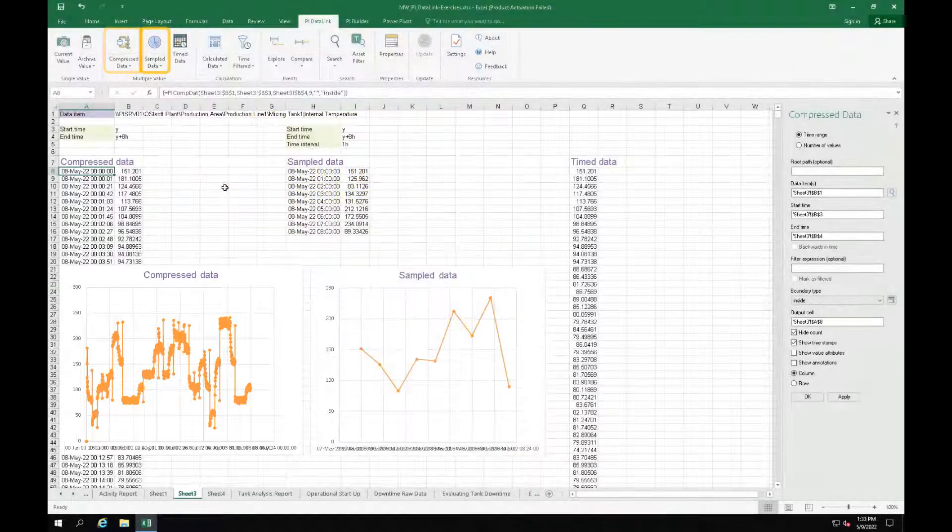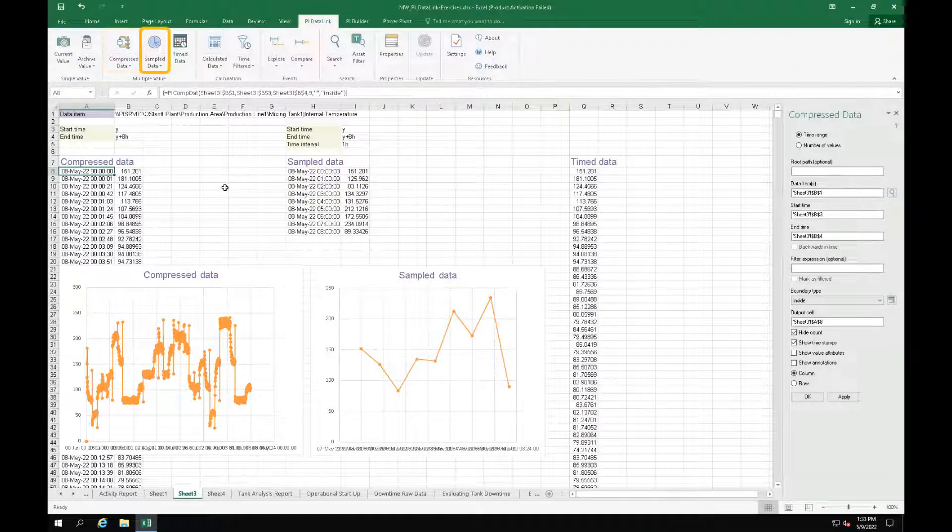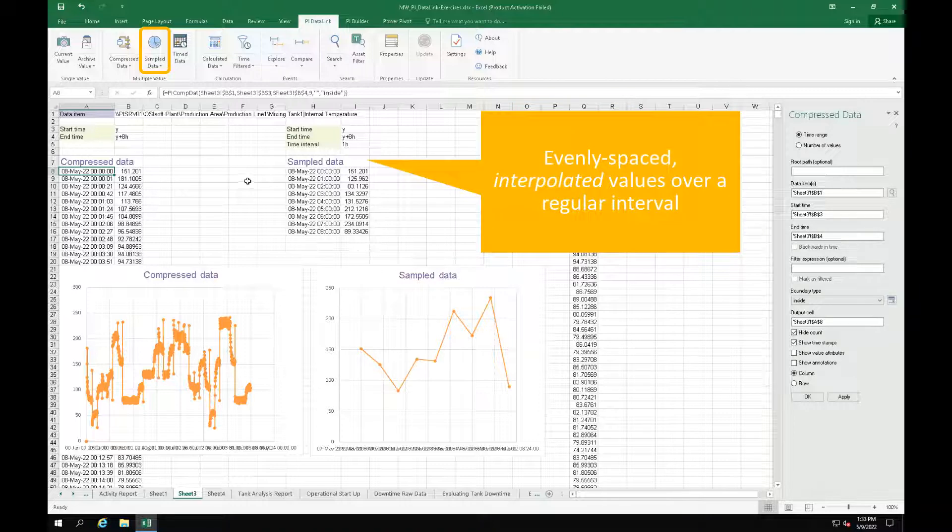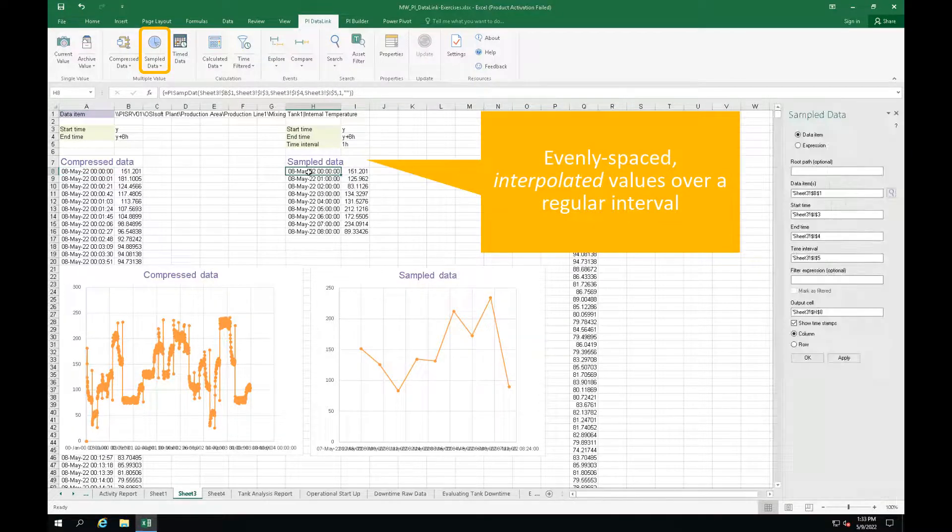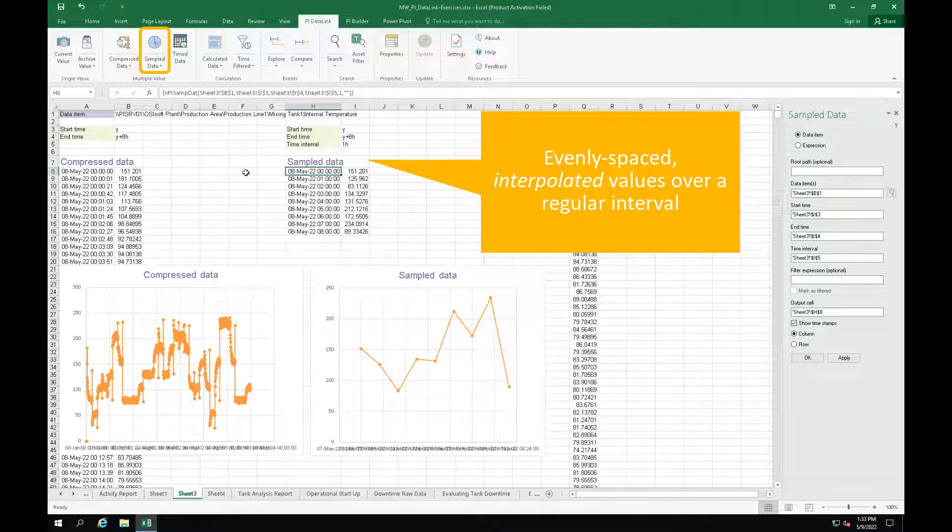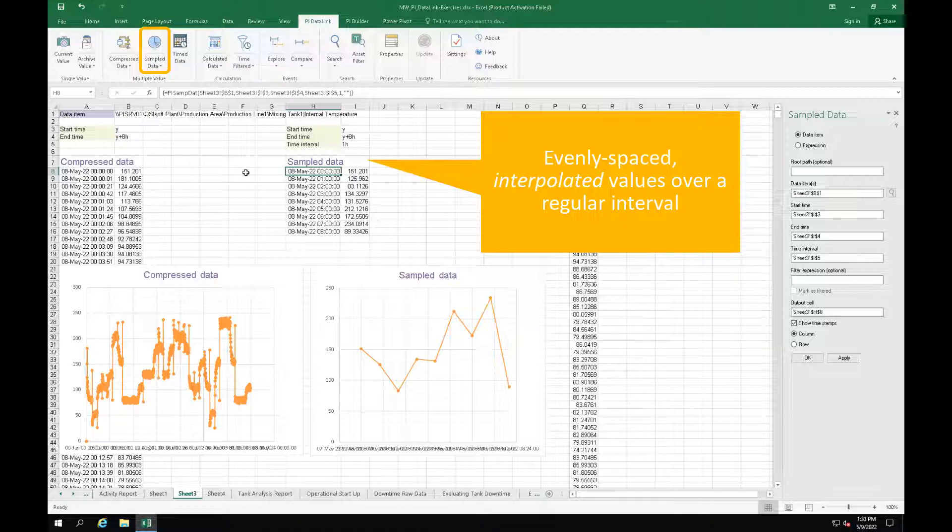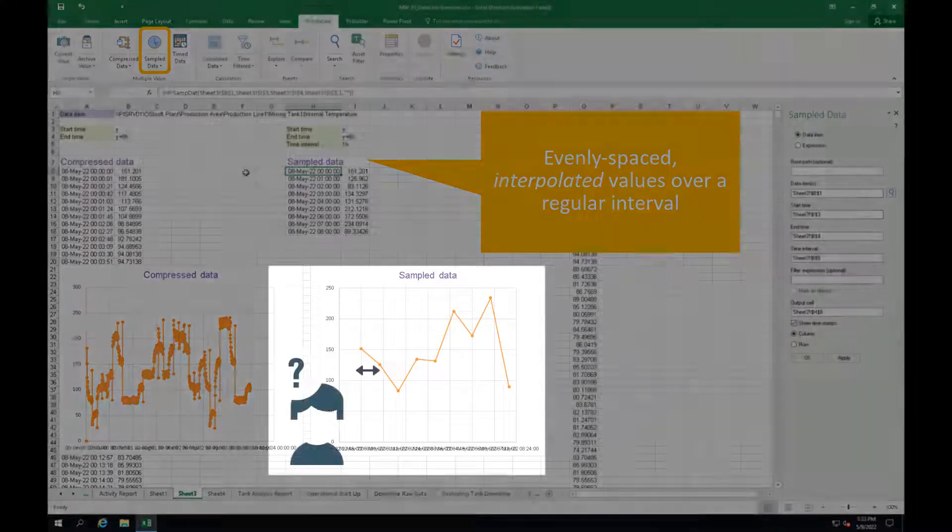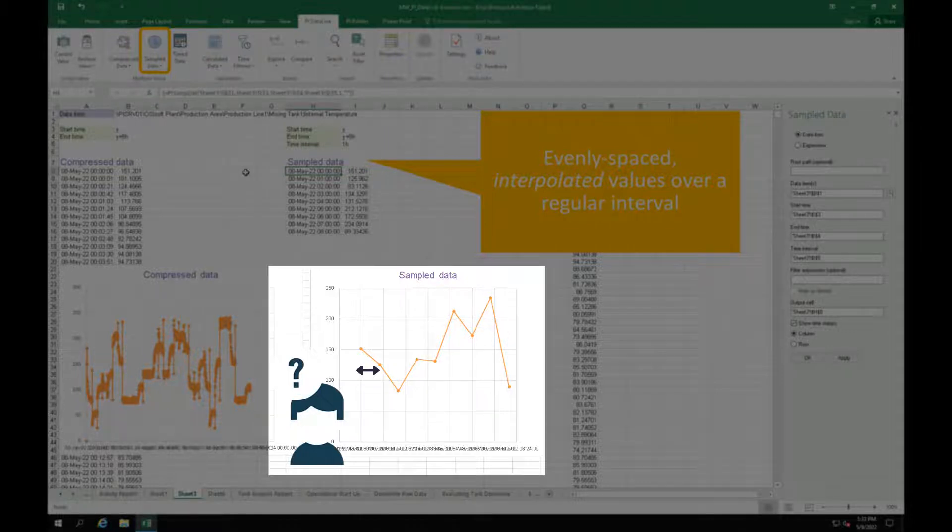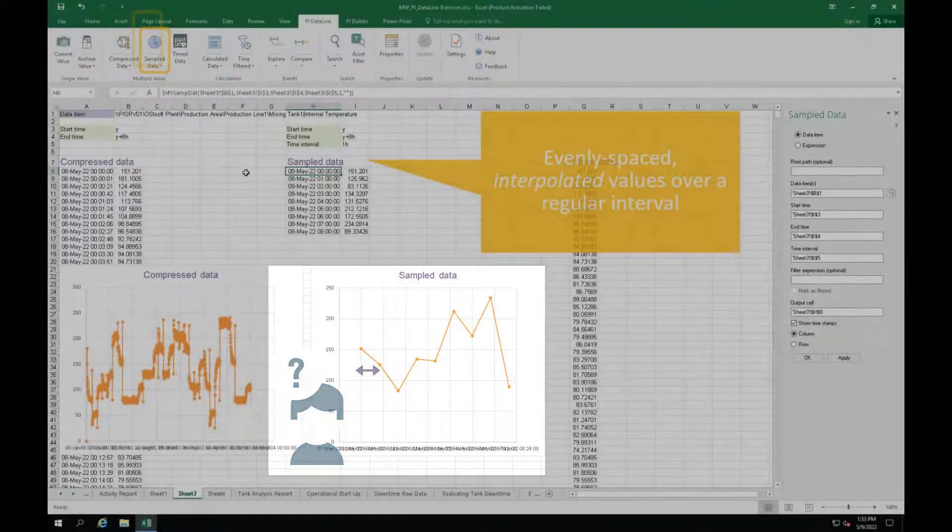The Sampled Data function returns evenly spaced, interpolated values for a PI Point or AF attribute over a regular interval. When you sample the values, you need to be careful and think about how you are going to sample in order to not skip any important events or peaks in your data stream. Looking at the graph with the SampleData function, you will have no idea what was happening in your process, for example between 9 AM and 10 AM here.